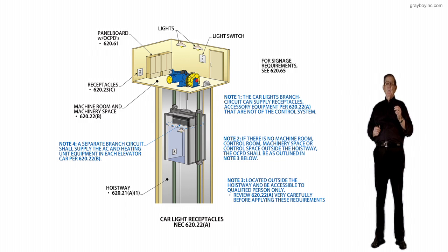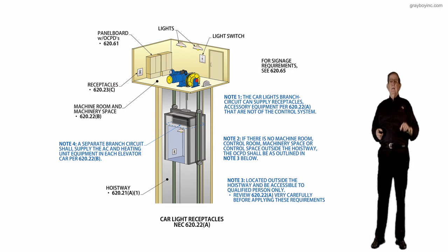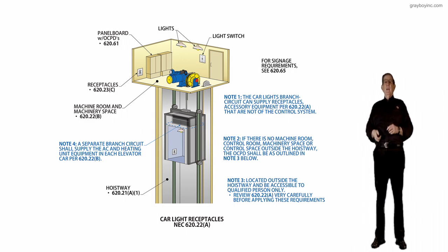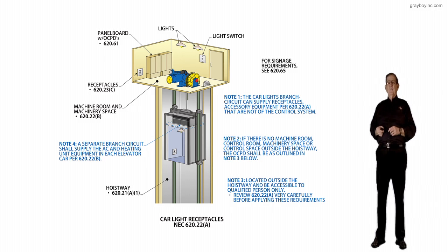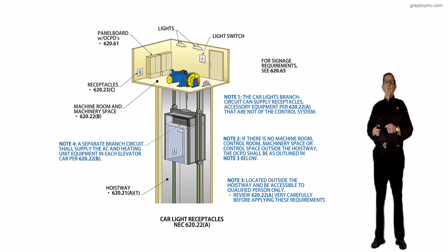so that you wouldn't mess up. So for example, if you go to Article 620, then it may say you can run a conduit in that elevator shaft and on each floor exit out and set a separately derived system and use that conduit with a grounding electrode conductor in it, a common grounding electrode conductor, to ground these transformers that are mounted on each floor.